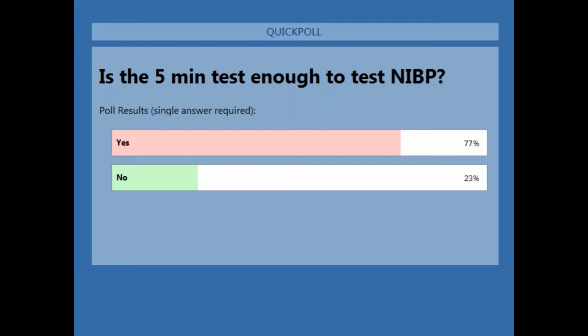And once we've done those two tests, leak test and the safety relief test, then we would do a static pressure comparison to make sure that if I have 120 millimeters of mercury on the patient monitor transducers, that I see 120 millimeters of mercury displayed on the screen. So whether that pressurization comes from ProSim 8 or whether it comes from the patient monitor, I want my ProSim 8 to tell me what's really there and compare that to what's on the display screen of the patient monitor in the service mode for NIBP, and evaluate several different pressure settings in order to do that. And most patient monitor manufacturers include more than one static pressure level when they want that NIBP performance, accuracy performance evaluated. So that would add some time.